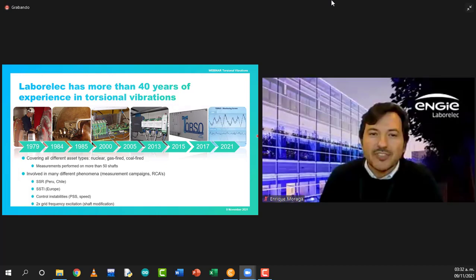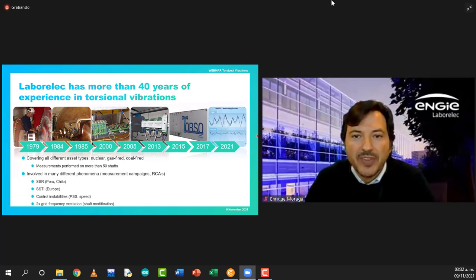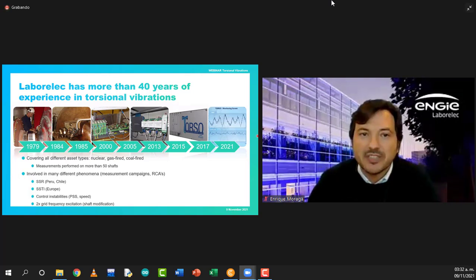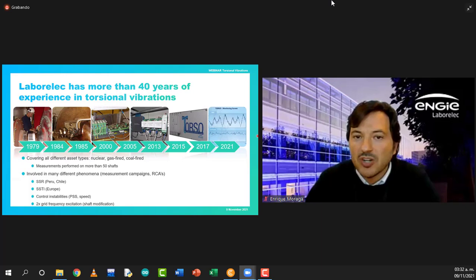Well, Laborelec and torsional vibrations have a long story together. Laborelec has been performing torsional vibration assessment and modeling for a long time. Back in the 80s, Laborelec started to perform the first measurements to check if a transient phenomenon had an impact on the torsional vibrations of a shaft line. Later, in the 90s, the criteria for torsional vibration became available. So I can say that Laborelec was one of the first companies in studying the phenomenon and the consequences in thermal assets. In 2000, Laborelec developed in-house the torso monitoring system and continued performing torsional vibration measurements.